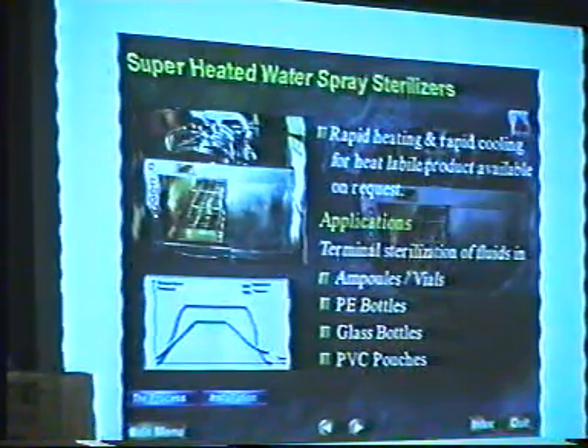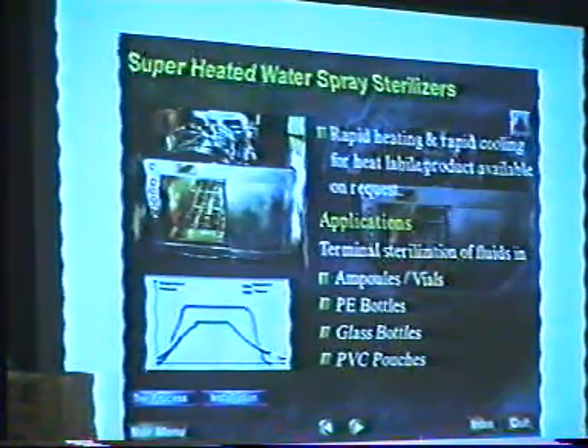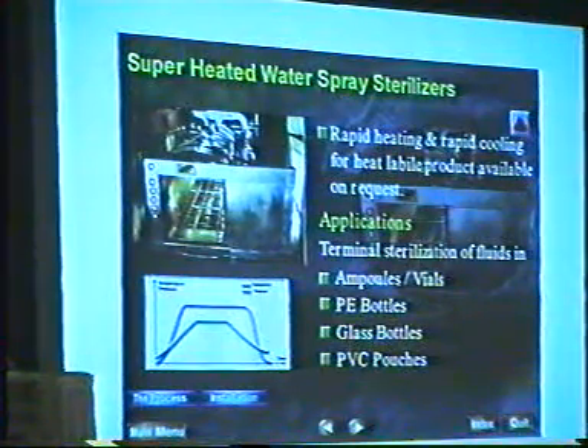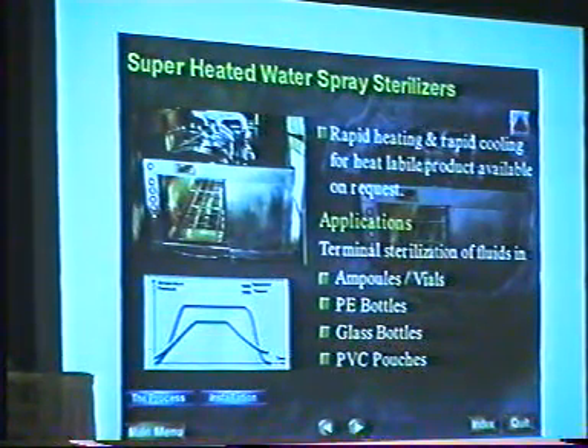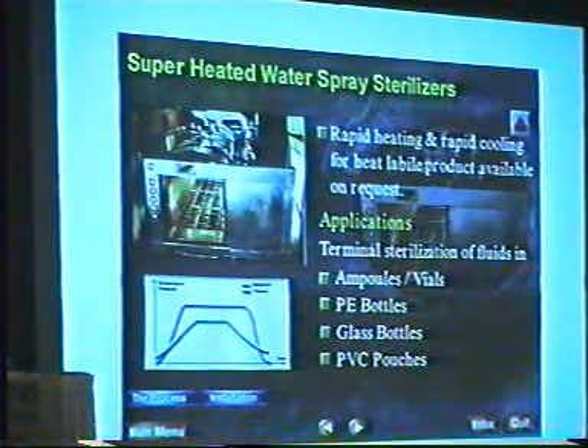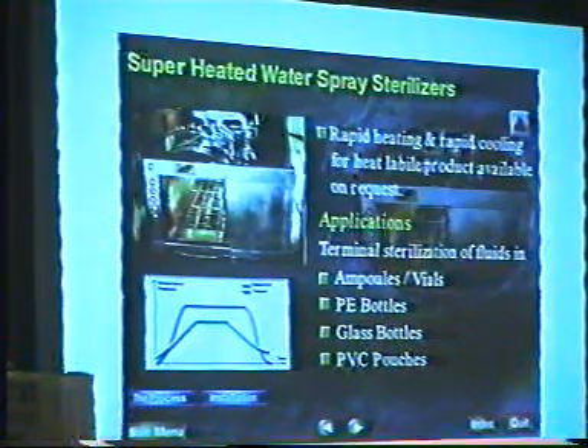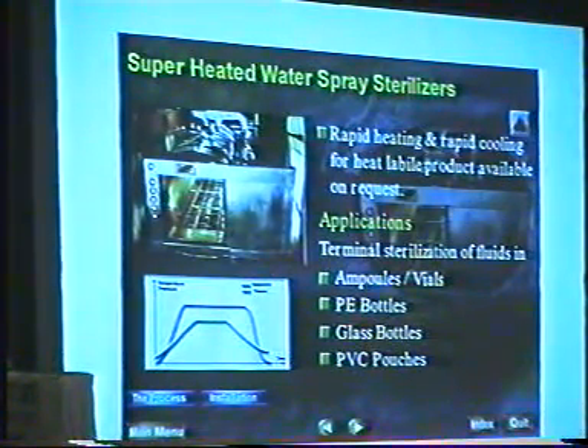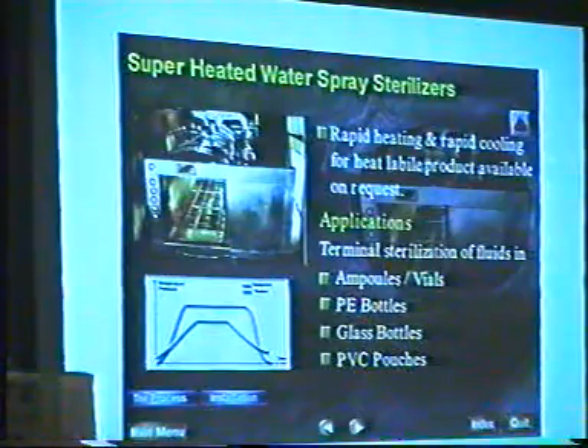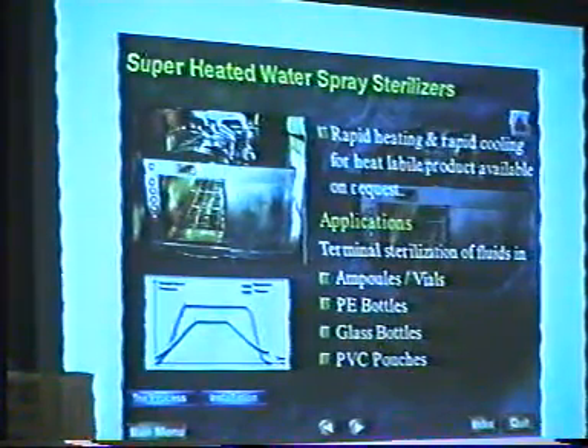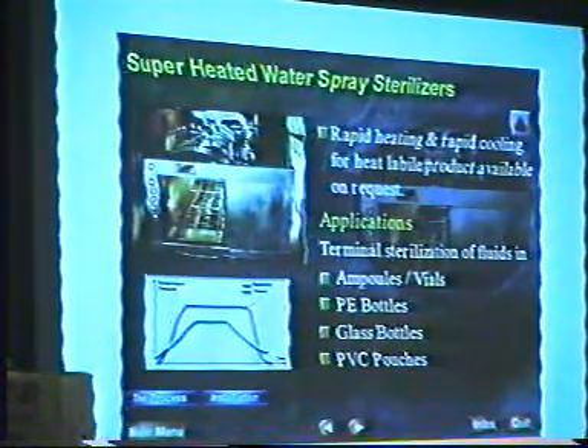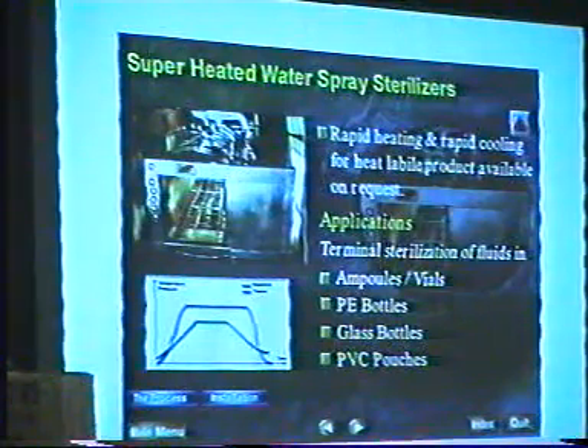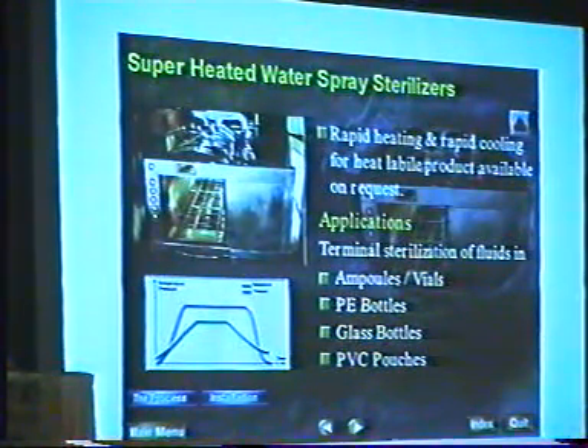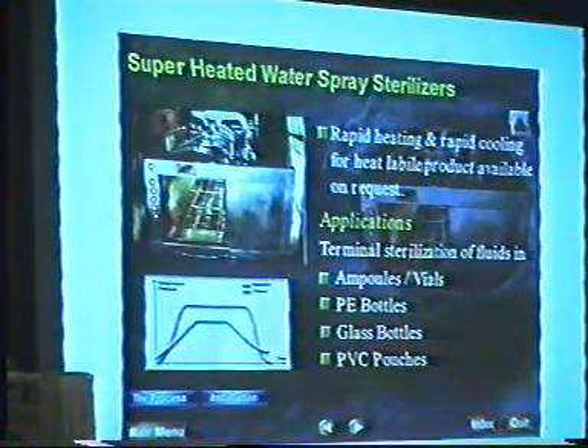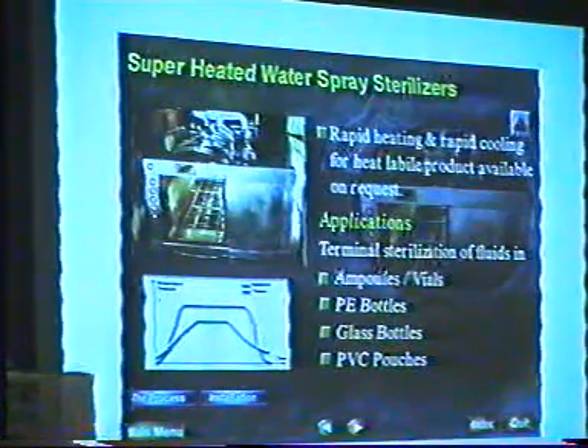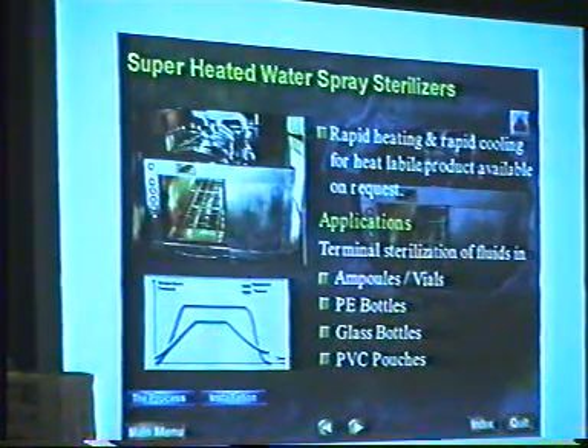Secondly, the speed of the process can be varied very greatly. Here I would like to give you one interesting example. A multinational company approached us for a medication which was to be sterilized in glass ampoules, but only with one condition: that heat up from room temperature to 121 must happen in 4 minutes, and cooling from 121 degrees centigrade to 60 degrees centigrade once again must happen in 4 minutes, or come to 30 degrees centigrade within 8 minutes.